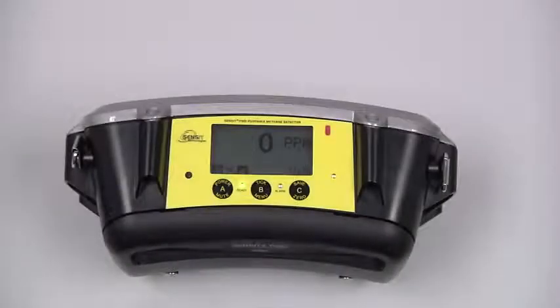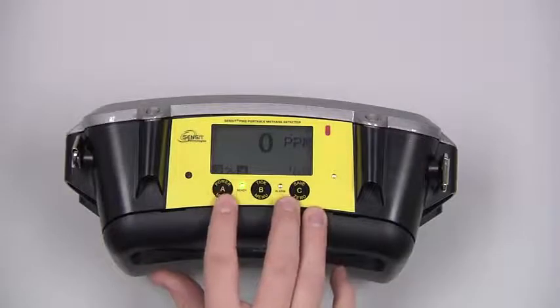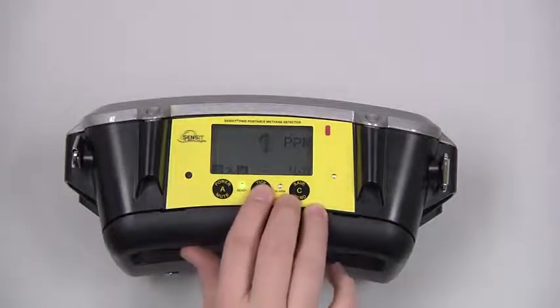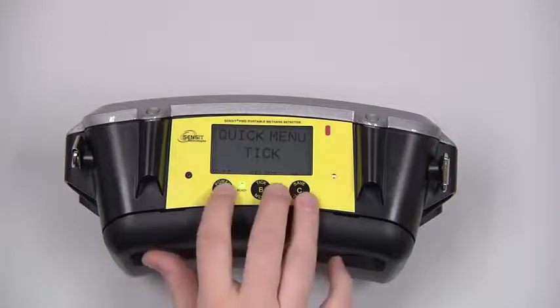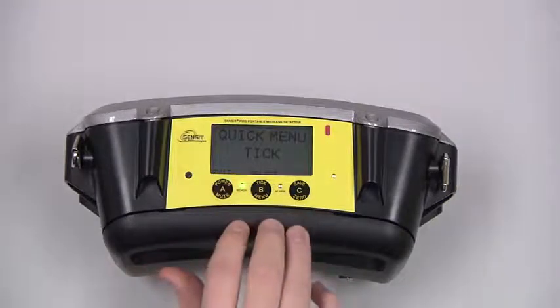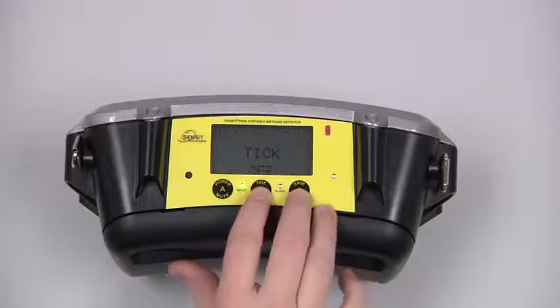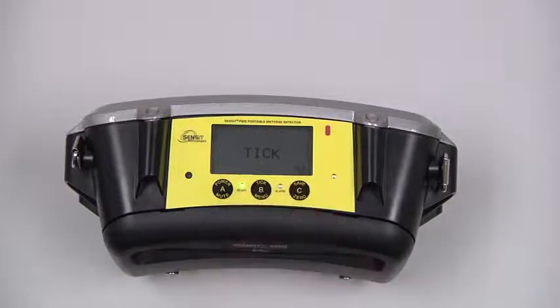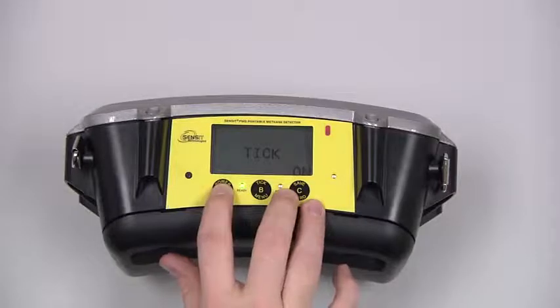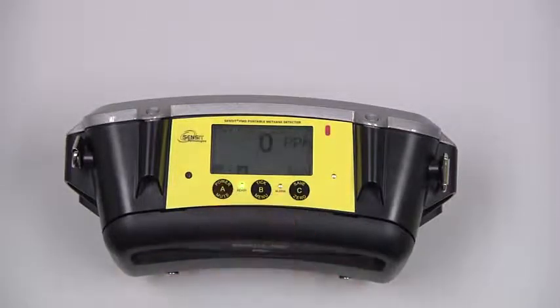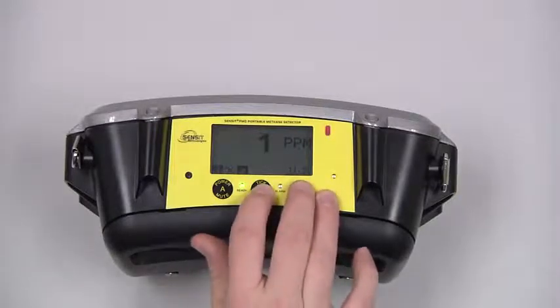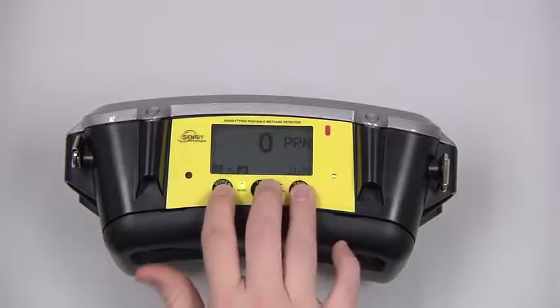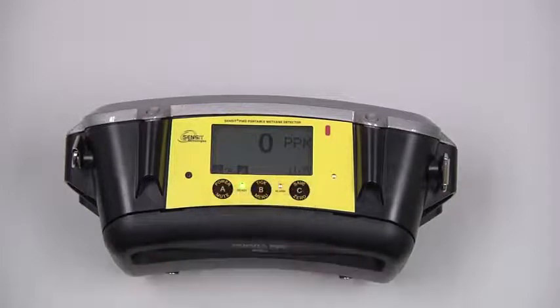During use, pressing and releasing the A button will mute an alarm. Pressing and releasing the B button will access the quick menu. From here, if we want to turn on the tick feature, we press and release the B button again. With the C button, change that to on, and exit back to the work display with the A button. And there's now an audible tick. As the instrument comes in contact with methane, the tick rate will increase. We can turn that off by pressing and releasing the A button.